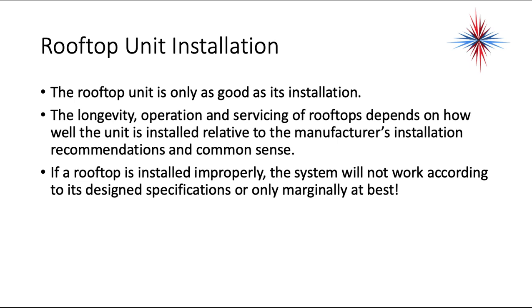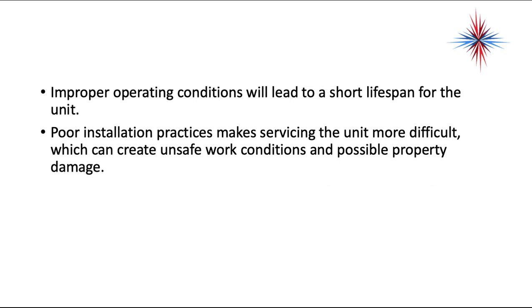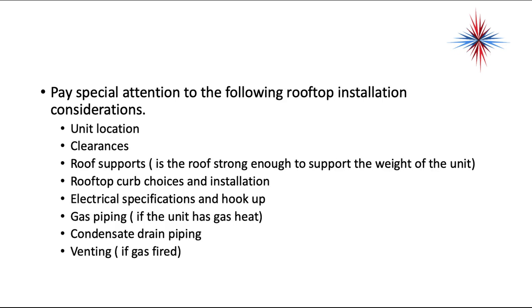recommendations and common sense. If a rooftop is installed improperly, the system will not work according to its design specification, only marginally at best. Additionally, it can actually cause building damage if it's not installed properly and can cause roof collapses. Improper operating conditions will lead to a shortened lifespan for the unit. Poor installation practices make servicing the unit more difficult and can create unsafe work conditions and possible property damage.